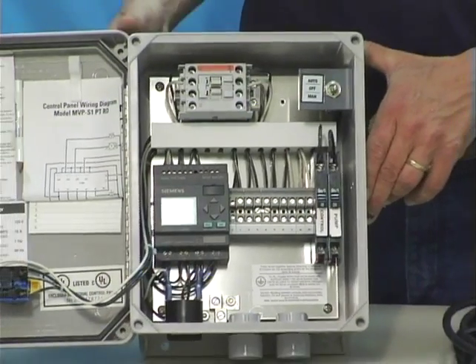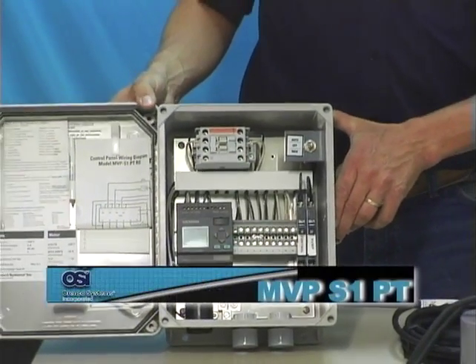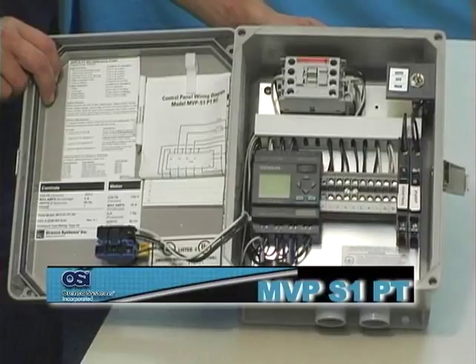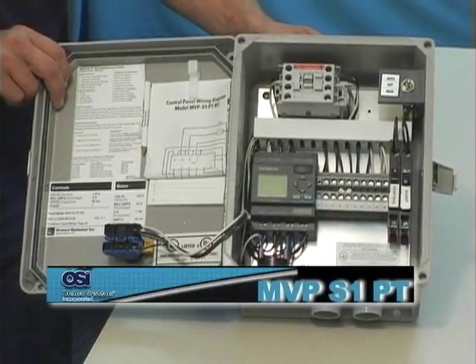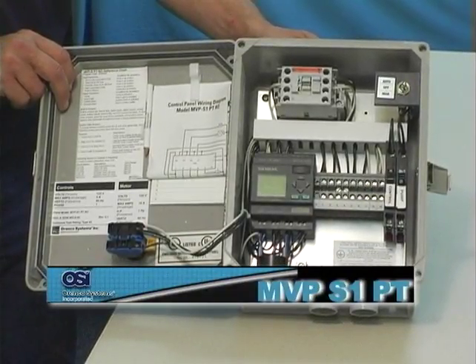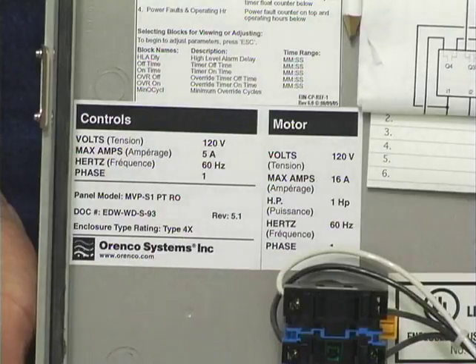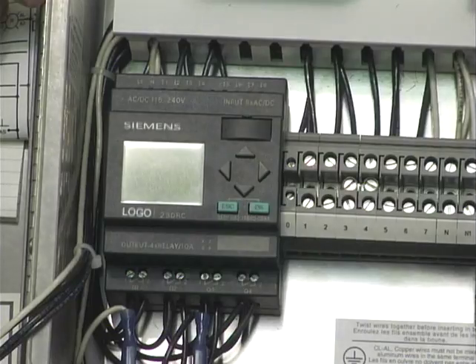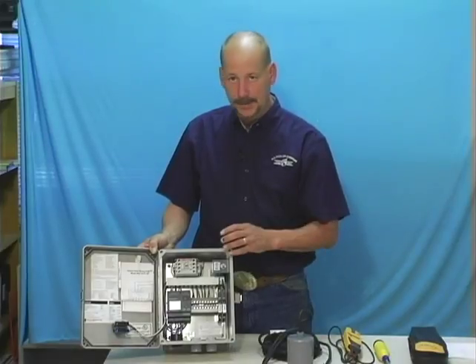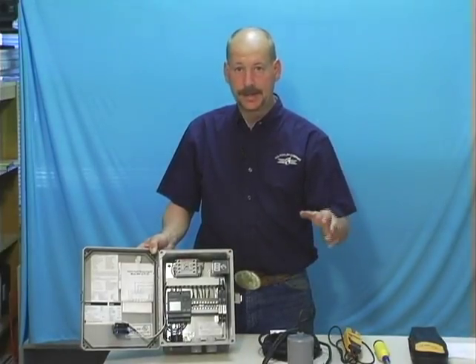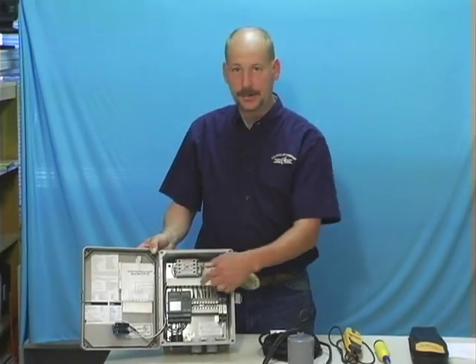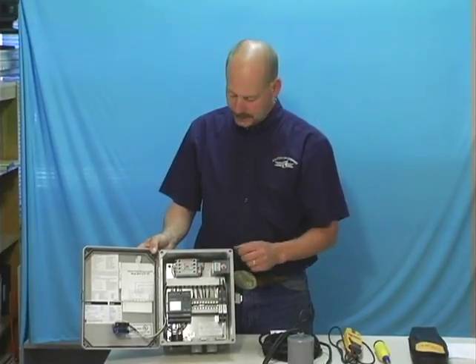HD Fowler carries many different control panels that either are on demand or timered. This happens to be an MVP control panel, and how you'll know that, there's two ways. One, the sticker on the door, and number two, it'll have the Siemens LOGO unit in it. Now with these LOGO units, we can use them for different options. You can use them either as a timer, or it could be a duplex alternating setup, and we'll use those instead of the black alternators.